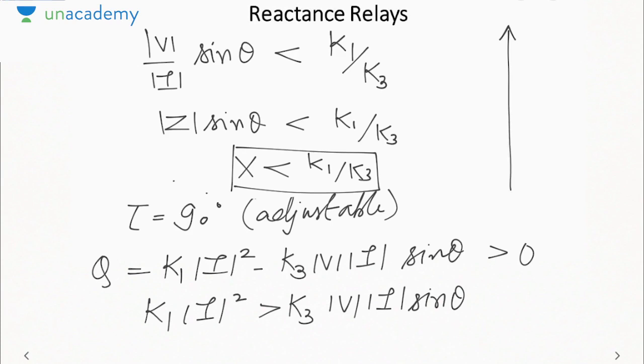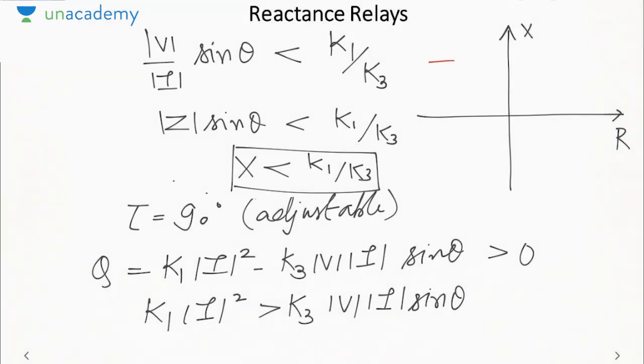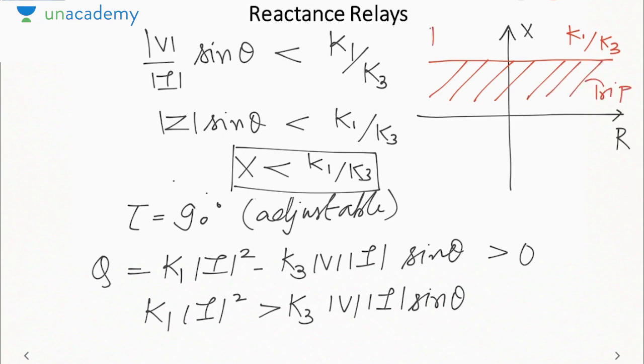So how does the characteristic look on an R-X plane? Here the boundary condition is X equal to a constant, like this. This value will be K1 by K3. The region below this is the operating region of the relay, that is the trip region. Above this it is the block region. That is how we characterize the reactance relay. Since it operates on the reactance, its operation is independent of the resistance of the power system or the transmission line.